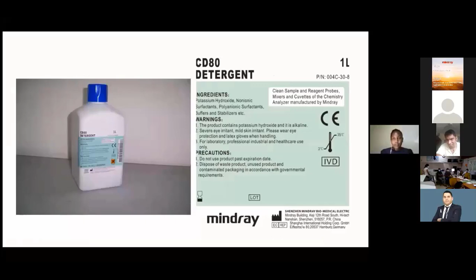So the second day, we procured a detergent. We received the detergent, and from that time, the issue is fixed. It's corrected, it's final, because with continuous monitoring, we've never experienced such cases anymore. Therefore, it became so clear that the problem was a result of reagent or sample carryover from the dirty probe. This probe was dirty because we were using an incorrect detergent. That's the detergent we're currently using, CD80 detergent from Mindray. Yeah, you can see it there as displayed on your screens.